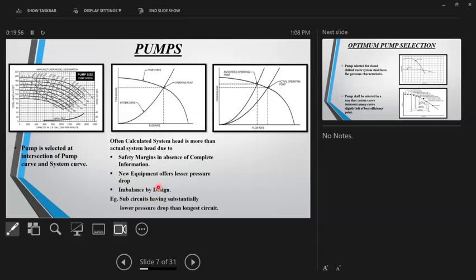So due to all this, what happens is you selected by calculations that the system would operate at this point. This was the flow rate and this was the pressure drop. In reality, the pressure drop will be less and you would end up over-pumping. So this would probably be the actual operating point when the system is new, and you would be forced to accept a higher flow rate. This is what actually happens in 99.999% of systems. Is this clear?